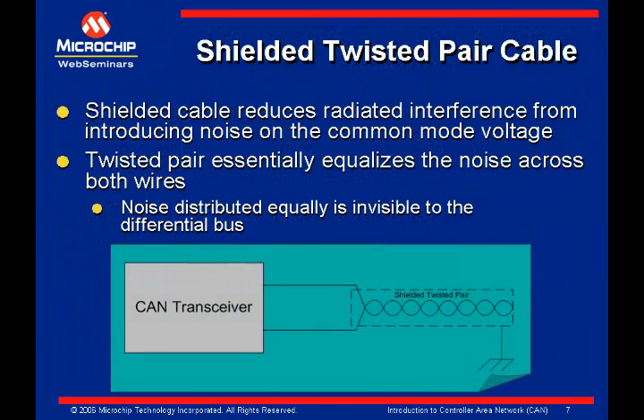Twisted pair wiring is a common method to reduce the effects of radiated emissions from external sources. Shielded twisted pair reduces the chance of noise coupling on the bus lines. Noise that does couple on the line is equally distributed to both wires and is effectively invisible to the differential signaling. The twisted pair solution is basically a filter and does not provide any protection from high energy electrical disturbances.